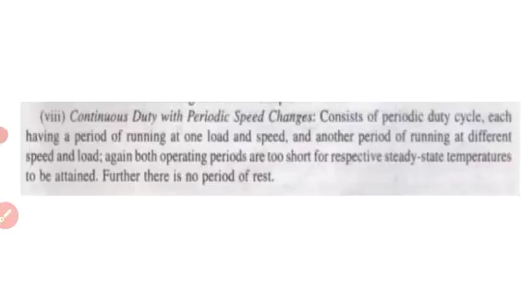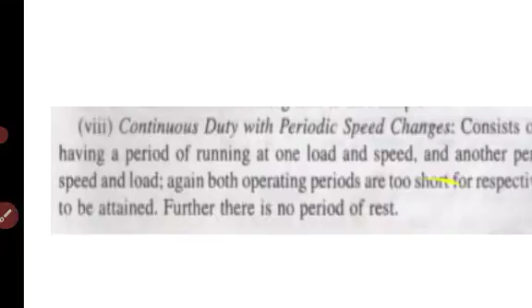Next one is continuous duty with periodic speed changes. It consists of periodic duty cycles, each having a period of running at one load and speed, and another period of running at a different speed. So first the motor is started at a particular speed, then the second period is on another load and speed. Again, both operating periods are too short for the respective steady state temperatures to be attained. Further, there is no period of rest. These are the two points you have to remember.